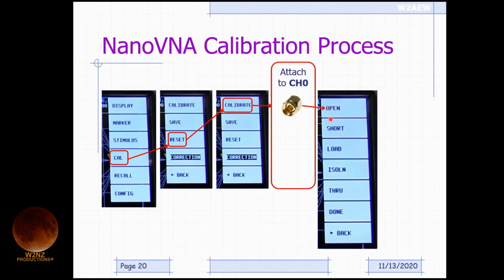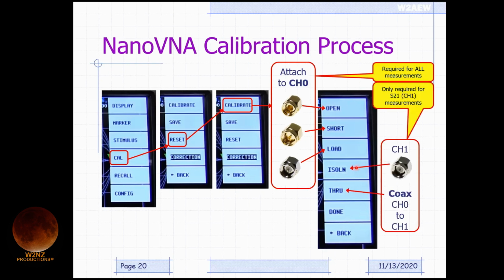Once you do that, it's going to prompt you with this menu structure for open, short, load, isolation, and through. What this is prompting you to do is apply an open circuit to channel 0, then apply a short to channel 0, and then apply a load to channel 0. These provide a reference the VNA uses to say, now I know what an open, short, and load look like after all of my connections. So I can calibrate out any of these errors and the interconnection to my device under test. Again, that's required for all measurements. The isolation and through measurements essentially measure crosstalk and the tracking errors for the second port. These are only required if you're making S21 or through measurements.